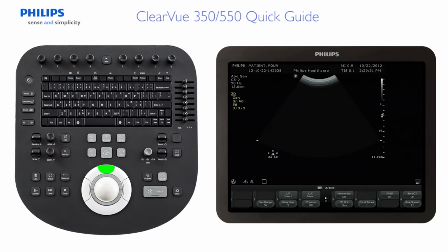The middle trackball button is located above the trackball and is used in certain procedures along with the trackball and trackball buttons. After selecting the transducer, press the Preset key to select the appropriate preset application for the patient examination. The preset menu will appear in the upper right portion of the display.